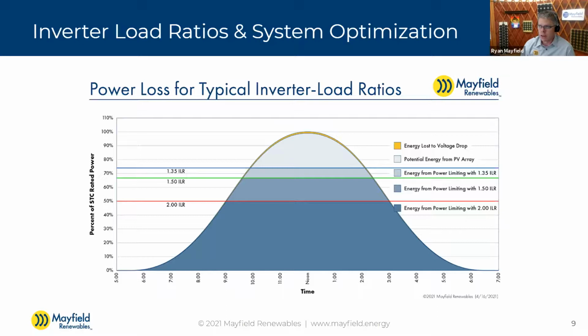Yeah, my experience, and what I've noticed in terms of the manufacturer spec sheets and how they state the limits - historically a lot of them had a maximum DC power input, or a maximum loading ratio stated on the spec sheet. I'm starting to just not see that on the spec sheets anymore at all. So most of them will now state a maximum current input, which to me is a much more valid way to state that.